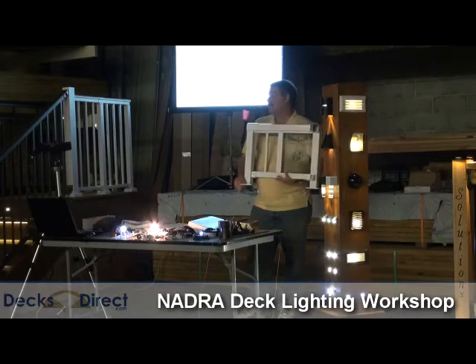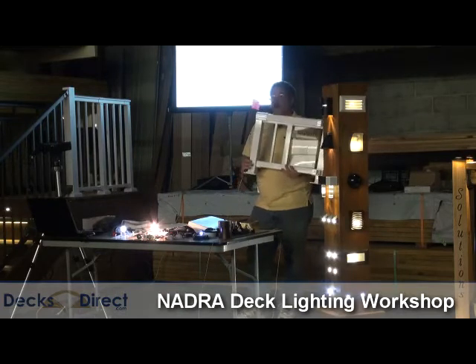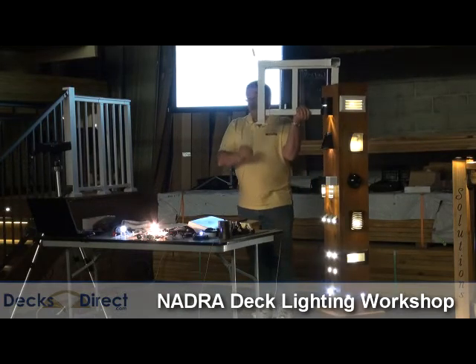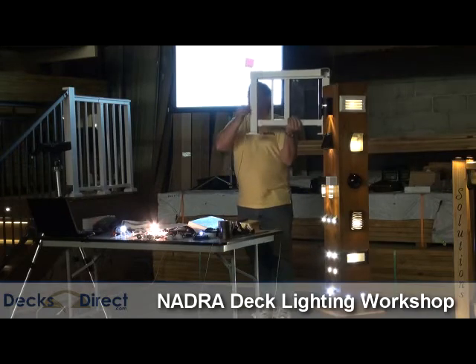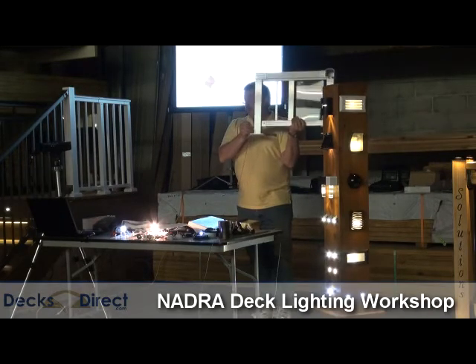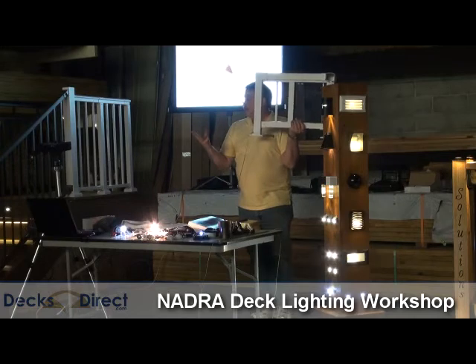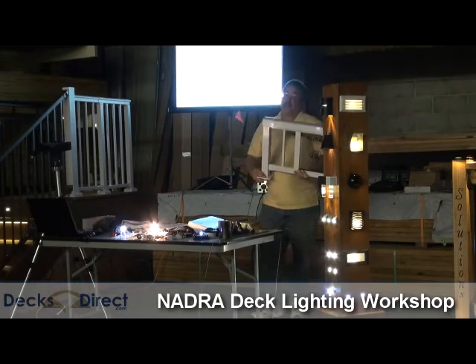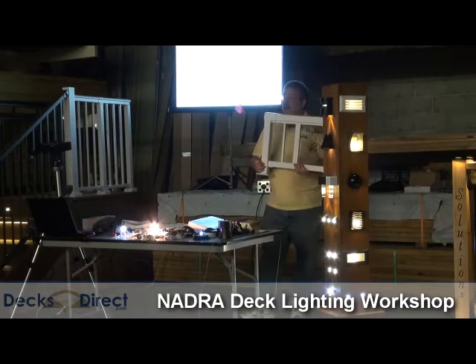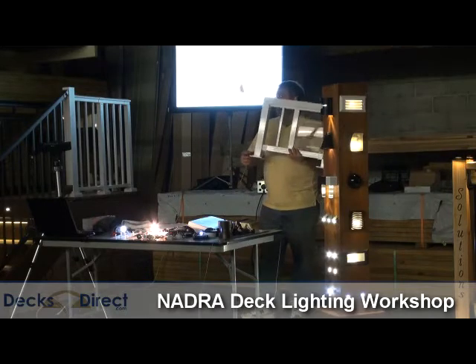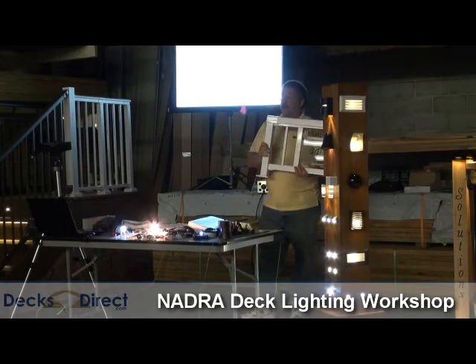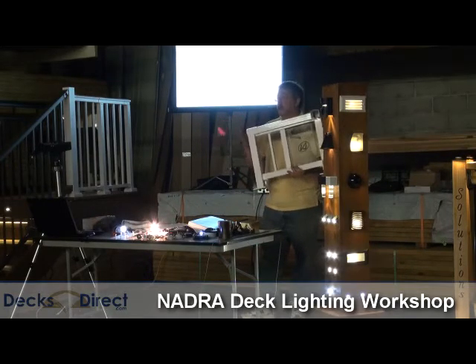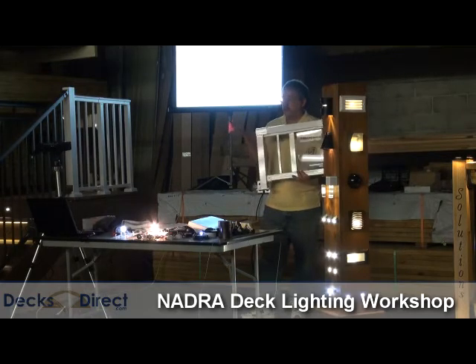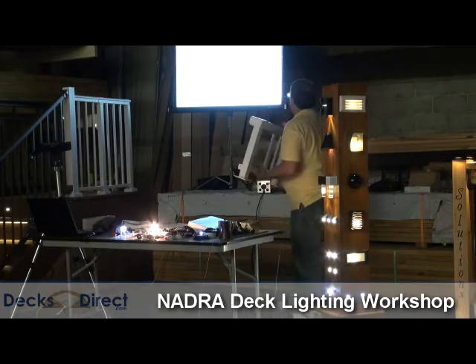Is that our responsibility? Maybe, maybe not. Think how cool it is if we put a little ground wire coming down, a number 8 wire, and maybe a little flag on there, so that when they have their hot tub installed and you've taken a picture of it and then somebody's hurt, it's like, guys, I told you this had to be done. This rail had to be grounded. I'm following the building codes. We just shed some liability so none of us are getting pulled into court when somebody gets hurt from these hot tubs with the different voltages on your deck.